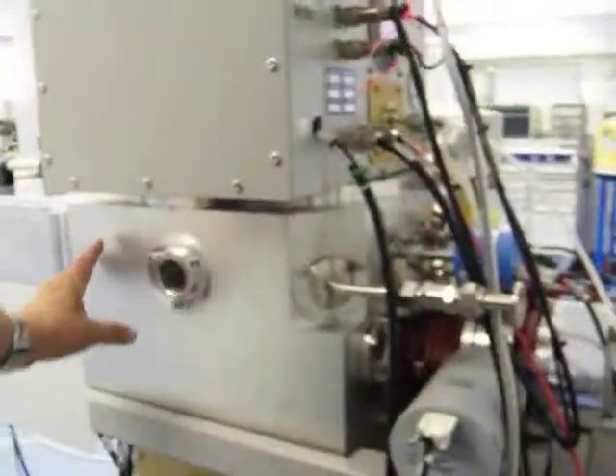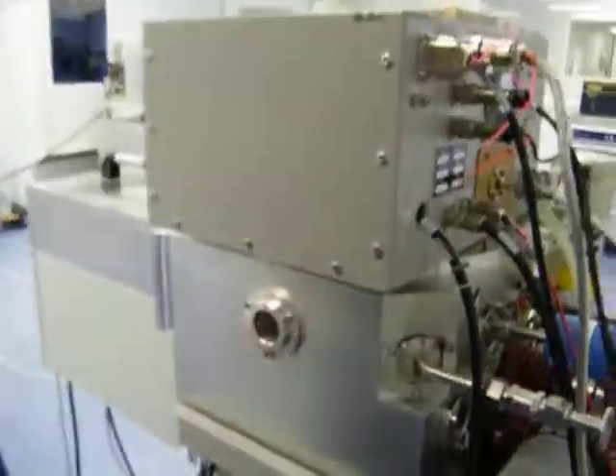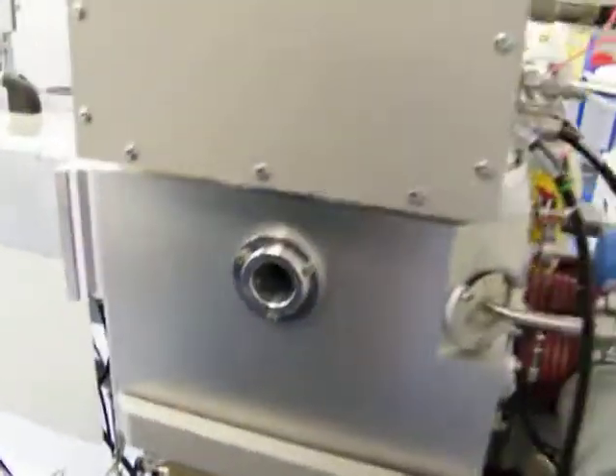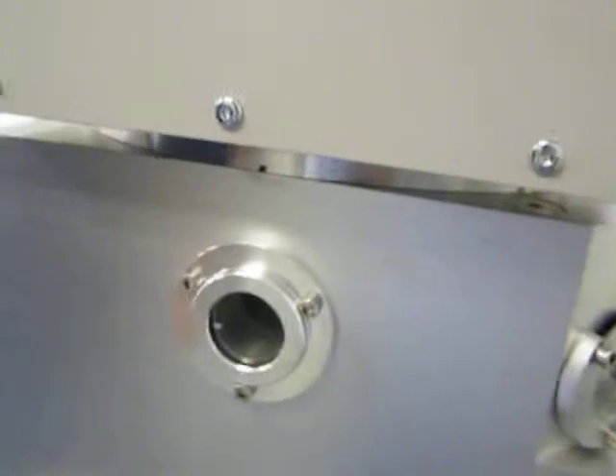O-rings and seals have all been replaced on the system. This particular customer requested Kalrez O-rings — all brand new, installed in the chamber. The chamber has been thoroughly cleaned. The windows here are new as well. A whole number of consumable and worn parts are replaced with new, such as these windows and all the seals and O-rings.